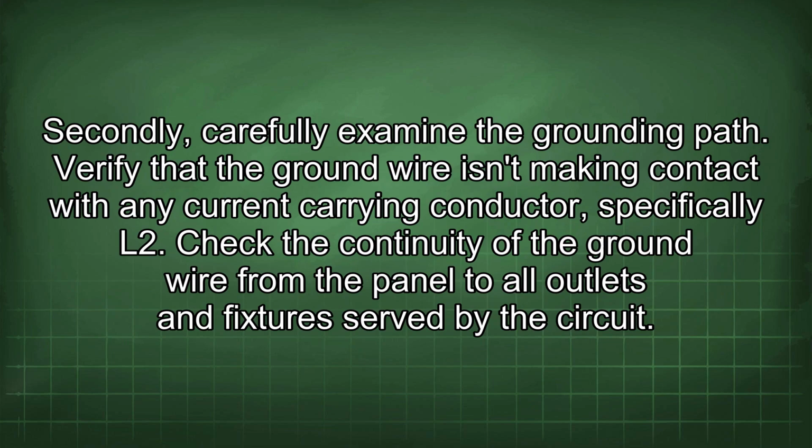Secondly, carefully examine the grounding path. Verify that the ground wire isn't making contact with any current carrying conductor, specifically L2. Check the continuity of the ground wire from the panel to all outlets and fixtures served by the circuit.